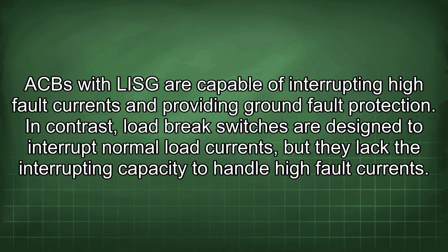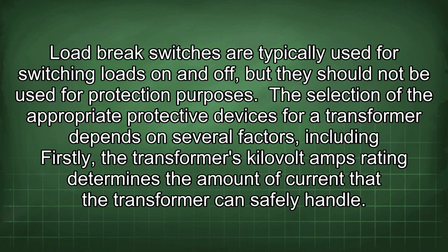In contrast, load break switches are designed to interrupt normal load currents, but they lack the interrupting capacity to handle high fault currents. Load break switches are typically used for switching loads on and off, but they should not be used for protection purposes.